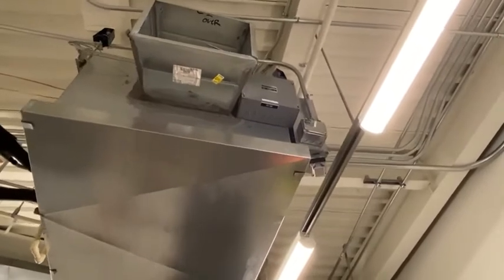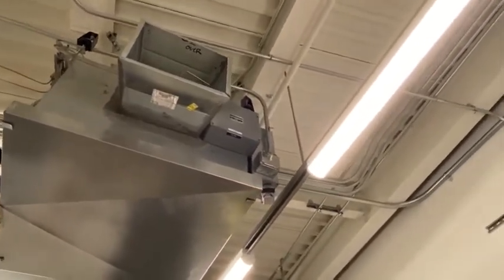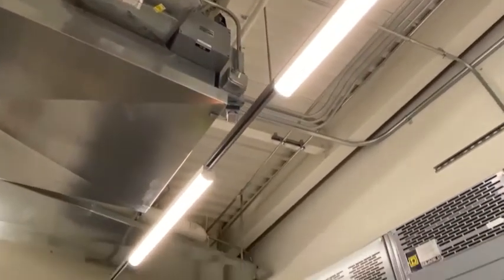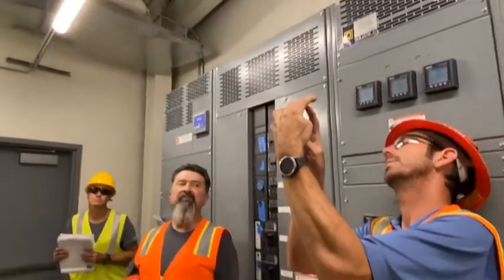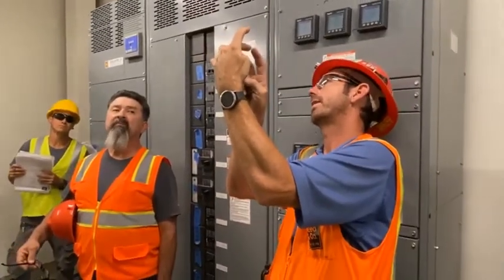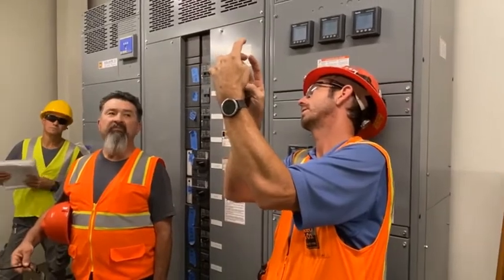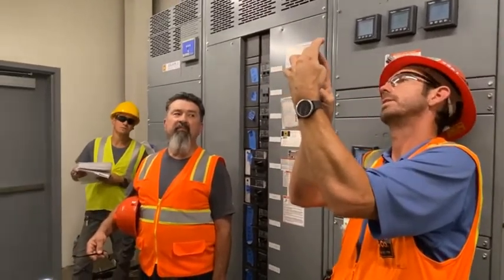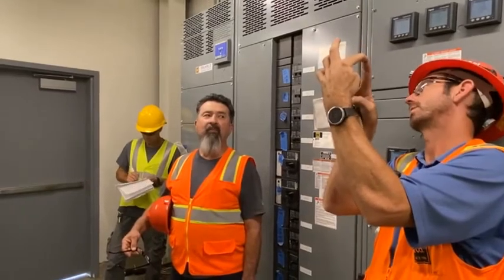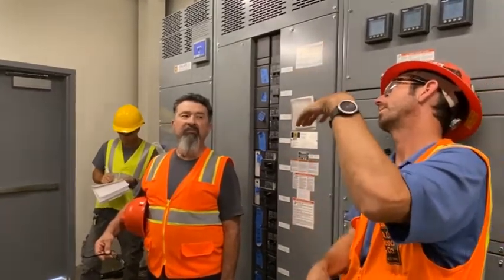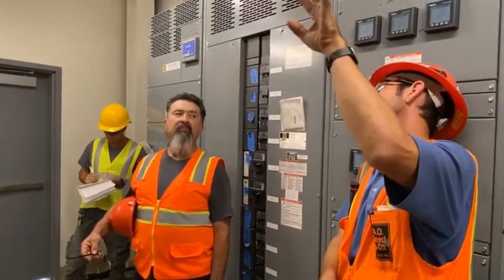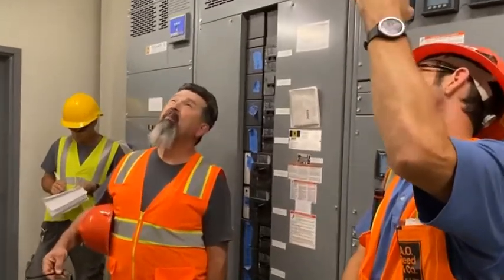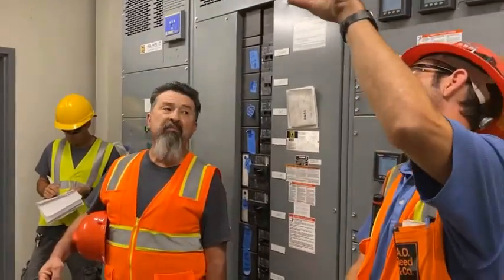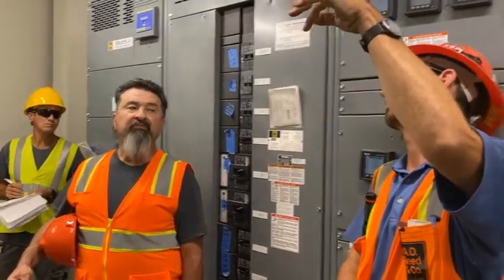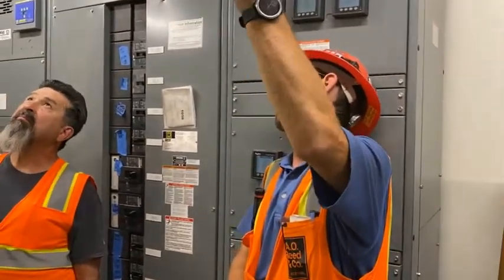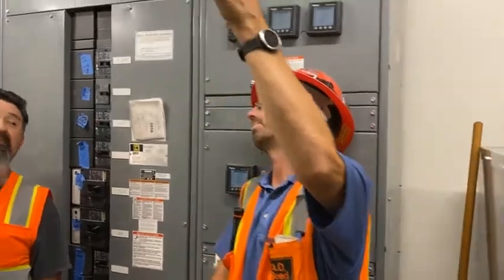So these right here, there's a terminal strip inside. There's 4 terminals. The middle 2 terminals are your speed signal. Make sure you look at the wiring diagram and follow which one's the neutral versus the actual 0 to 10 volt signal. And then the ones on the outside are going to be your 24 volts that power any external devices and also power the motor itself. Okay. So that speed motor does take 24 volts to power it up, and then it also gets a 0 to 10 volt signal to run. It also is using 277 volts to spin the motor.